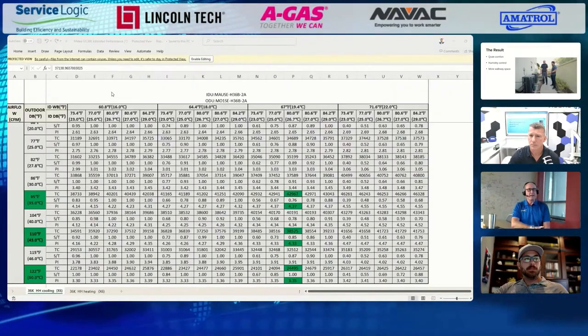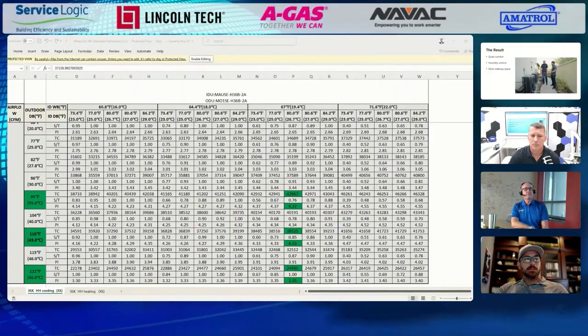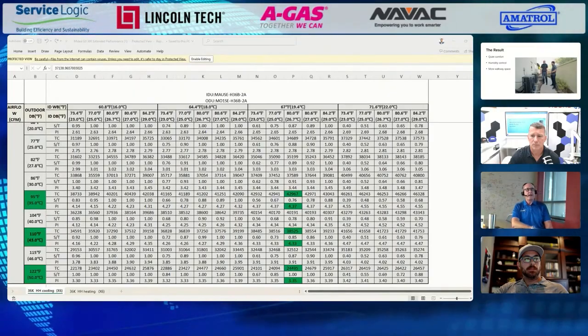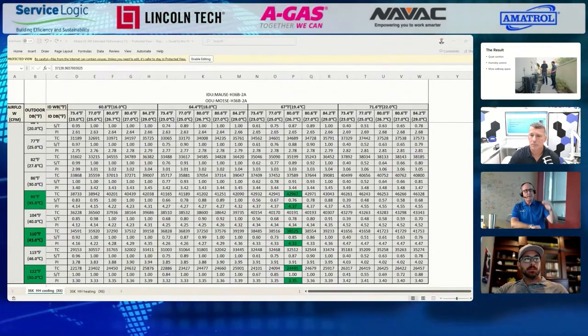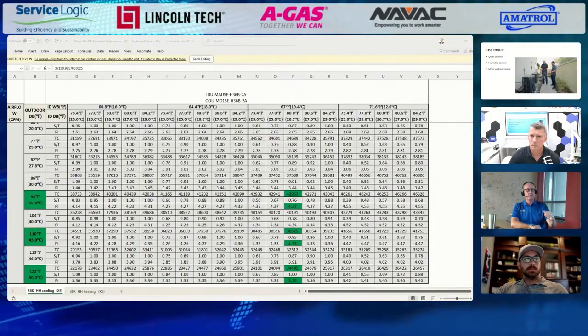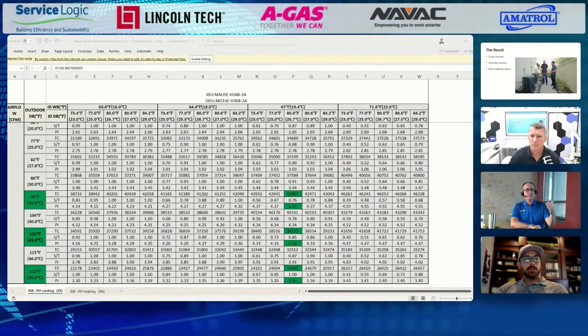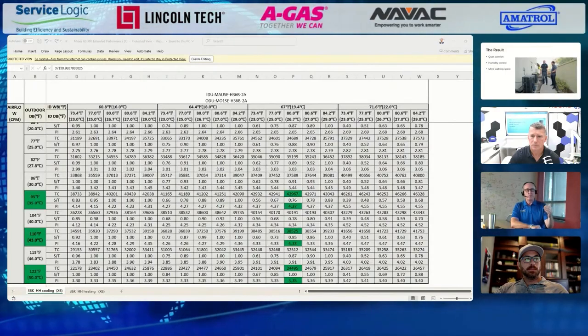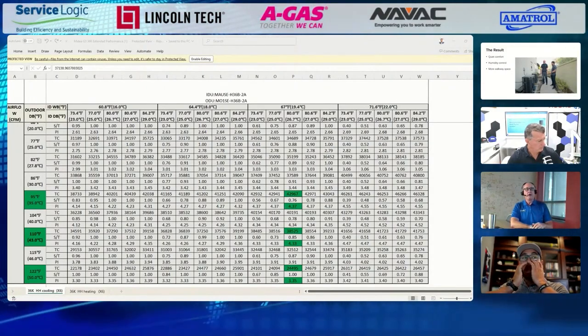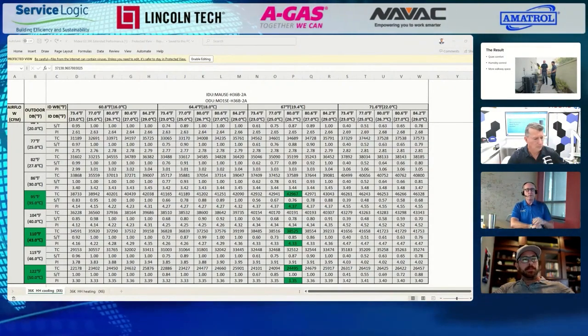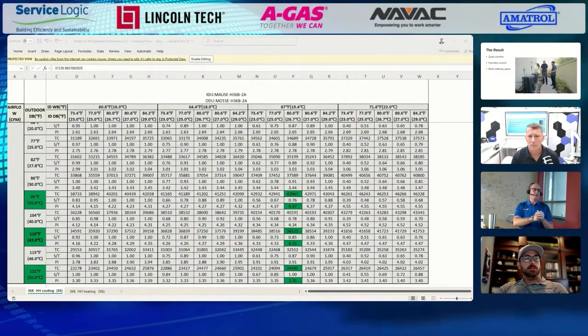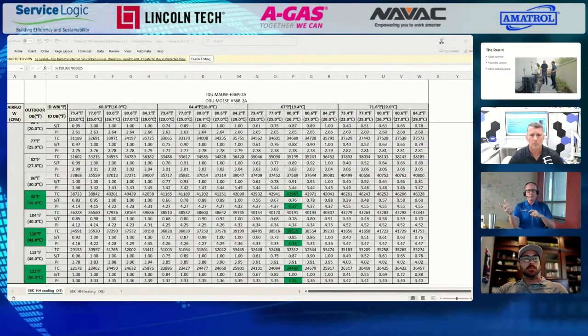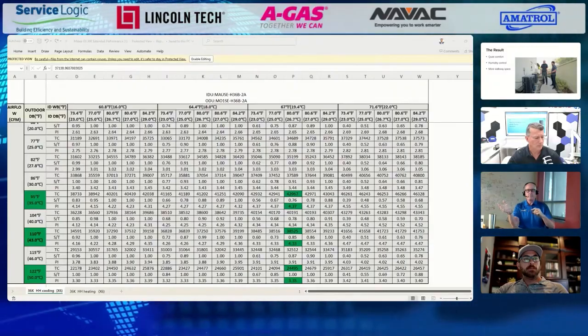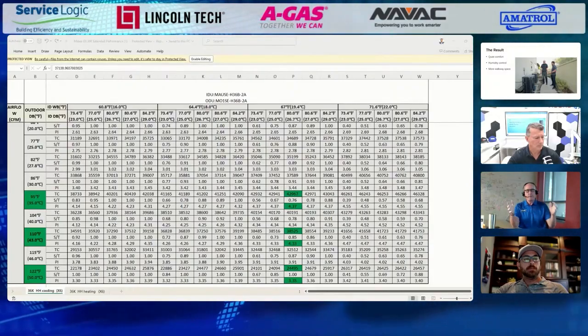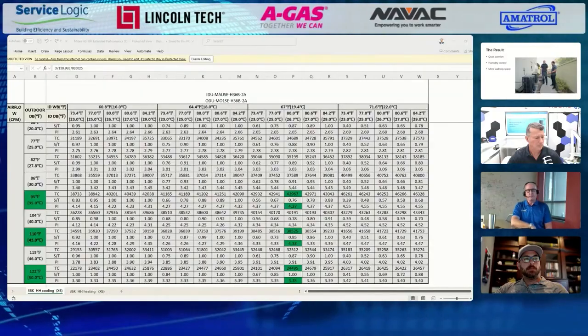What we find out is when we look at that, we actually had the ability to downsize him by a full ton, and actually outperformed the old system by downsizing by 12,000 BTUs while keeping him more comfortable, which, as you know, stops that short cycling. That's where the discomfort comes in, short cycling both heating and cooling. So we went from a single stage to a true all-season heat pump, and we had both covered, and he's way more comfortable than he's ever been.